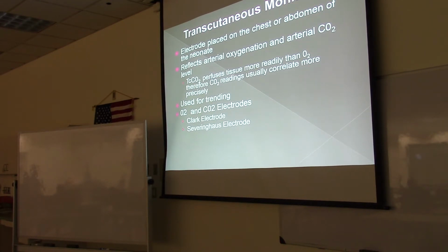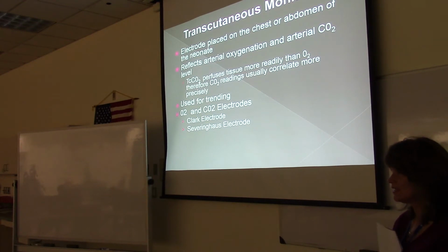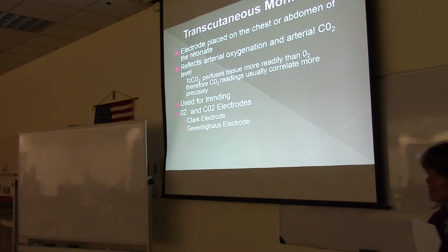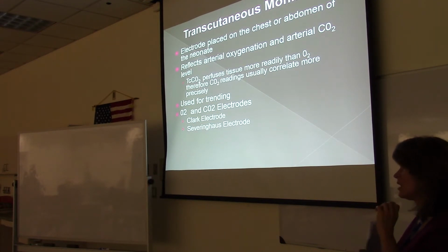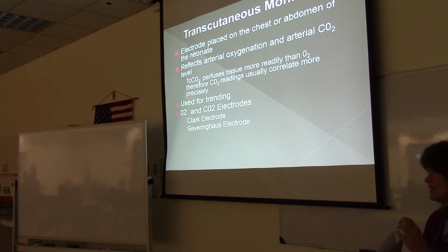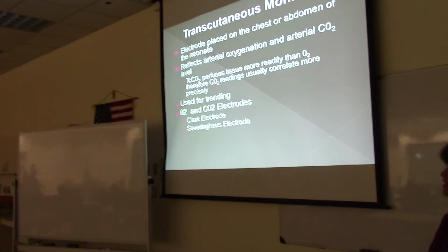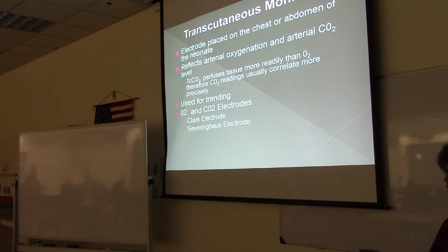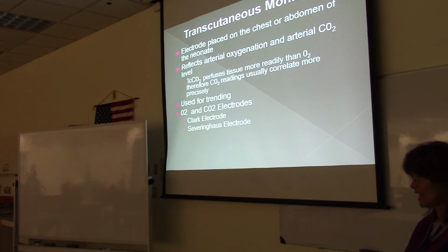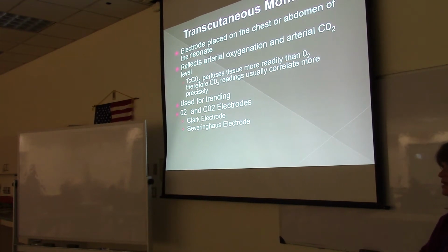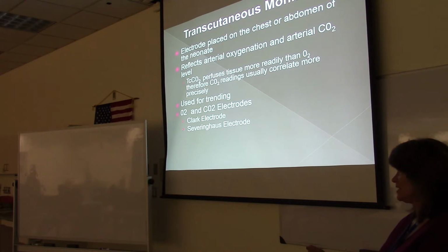So transcutaneous monitors are electrodes that are placed on the skin, and they can tell how much oxygen is in arterial blood, how much carbon dioxide is in arterial blood, just from sitting on the skin. The way that it works is that there are little warmers in the electrodes, and it warms up the skin. And when you warm up skin, you bring arterial blood flow close to the surface of the skin. Then oxygen and carbon dioxide will diffuse through the skin, and it can be detected at the surface of the skin. Carbon dioxide, very easily.